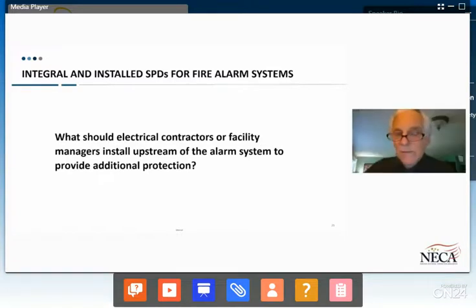I'd like to add also that when we talk about residential systems, the code-required surge protective device at the service entrance is just the first line of defense. What homeowners ought to do, just like I've done, is provide high quality type 3 surge protective devices at the loads. Right now, sitting in front of my computer in my living room, my computer's plugged into a surge protective strip that isn't a cheap one, it's a good one, and that provides additional protection within this facility.